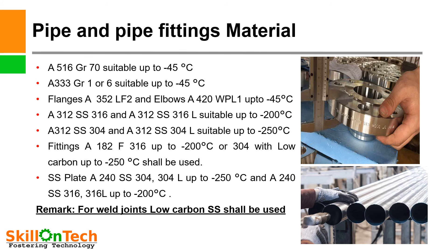A312 SS316 and A312 SS316L are suitable up to –200°C, so pipe and pipe fittings can be made of SS316L or SS304L. A312 SS304 and A312 SS304L are suitable up to –250°C. For fittings, A182 F316 or F304 with low carbon shall be used. SS plates A240 SS304, SS304L, A240 SS316, and SS316L can be used for plate material. For weld joints where welding is essential in pipes or fittings, low-carbon SS shall be used; otherwise, chromium carbide precipitation will occur and the material will lose its strength.